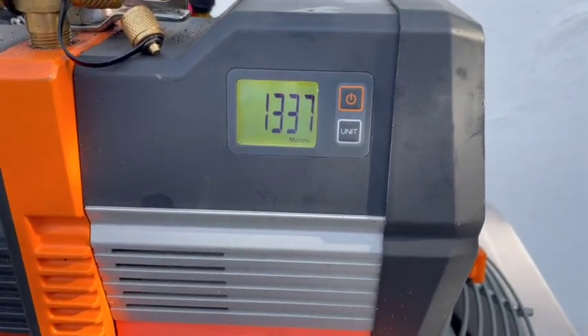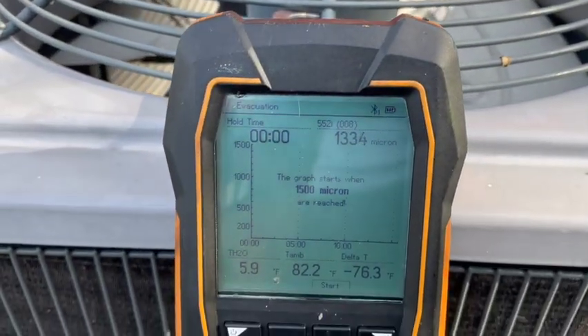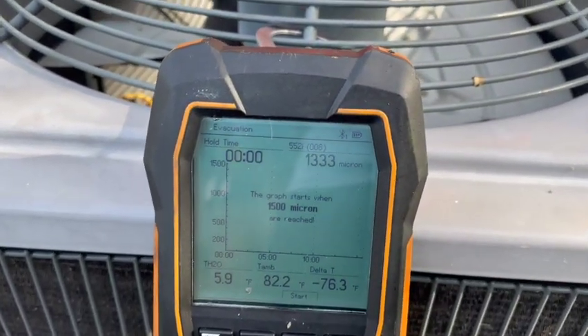It has this little vacuum gauge here, which is basically useless — it doesn't tell me the actual system vacuum. Although in this case it's pretty dead on; usually it has a significant difference, but for whatever reason today it's pretty dead on.